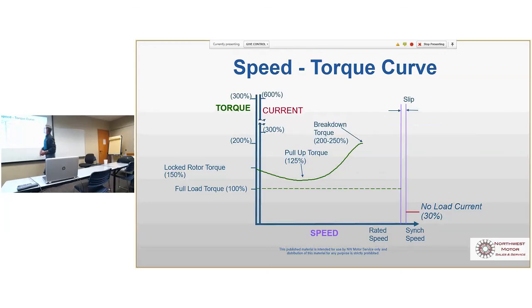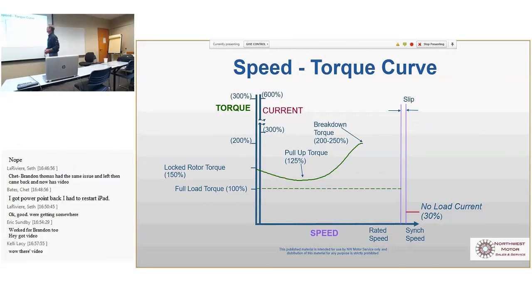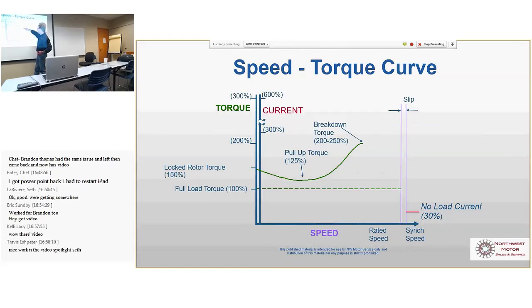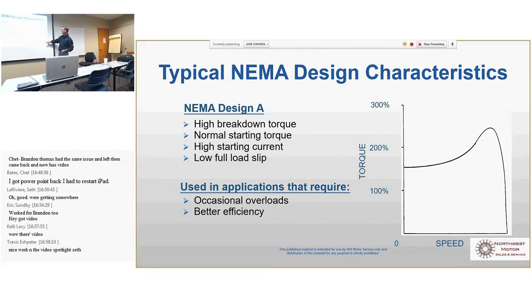So there's a lot of different lines here. But let's just assume here we are starting. So when we go to start the motor, we get 150% of torque right when we go to start. It doesn't last long, just for 15, 20 seconds, so long enough to accelerate the load. Then it drops down. The lowest point on that curve is called the pull-up torque, and at this grade, it's 125%. And it goes back up, and at this point, this is the most torque the motor can produce. In fact, it can't produce it very long. It drops back down here to full load torque. If you keep loading it up, it goes to 0 speed. So if you overload it more, it just stops.